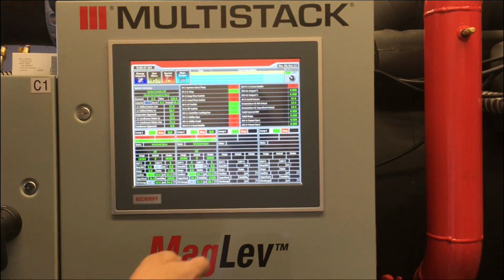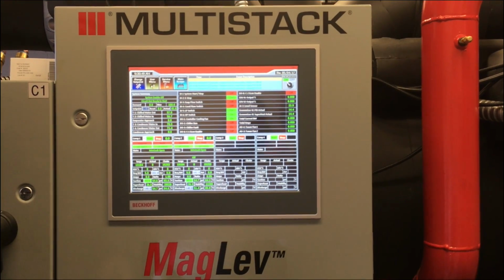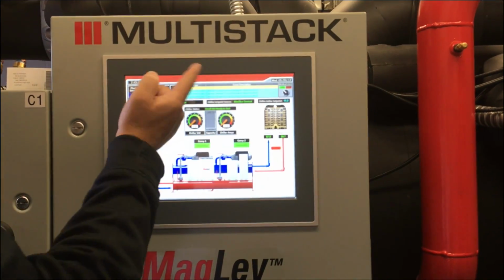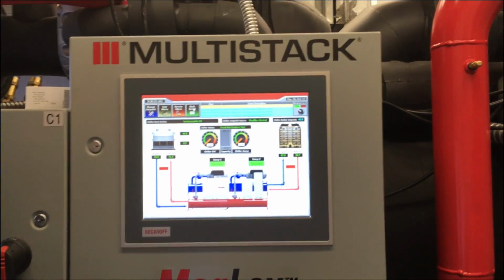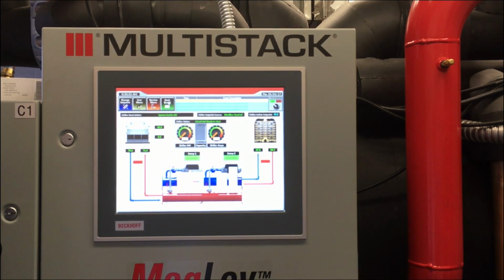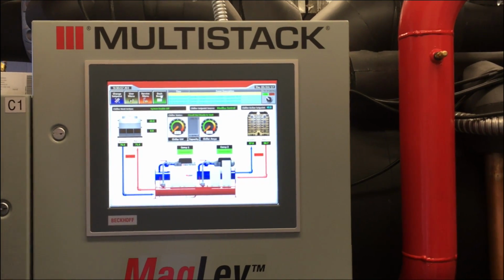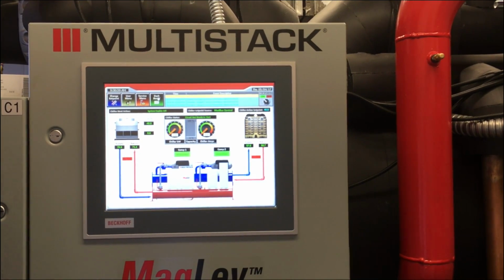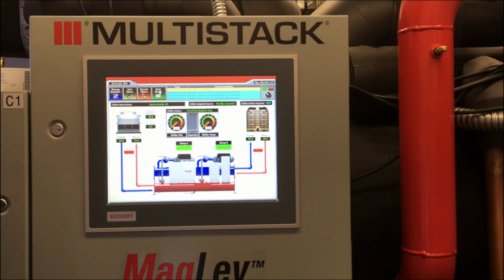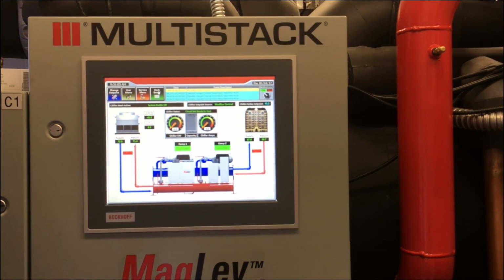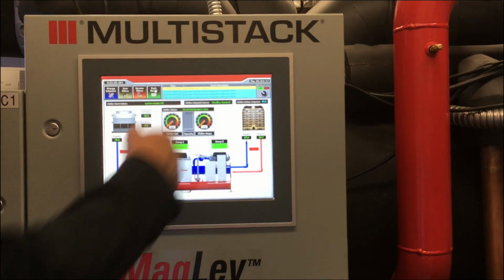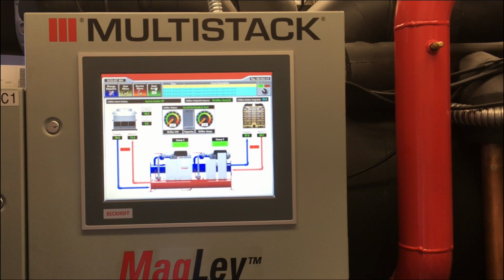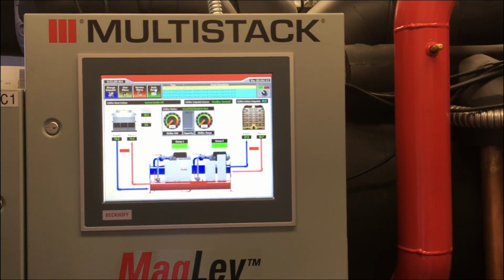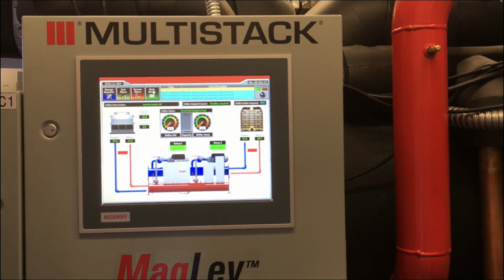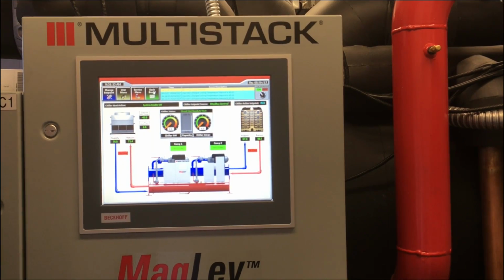So, back to main screen. This is pretty much the screen you guys will look at more than not. It's the basics: chill water in and out, tower water in and out, lets you know if a compressor is in alarm, gives you your kW, your capacity. It still gives you this screen up here, so you know if anybody's touched anything. I don't know if you guys log chillers or not. For logging, it's a great little screen.